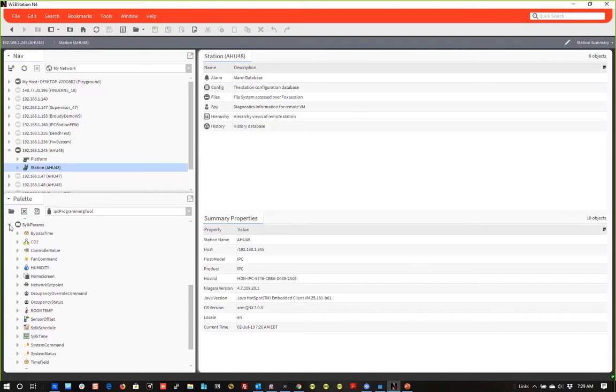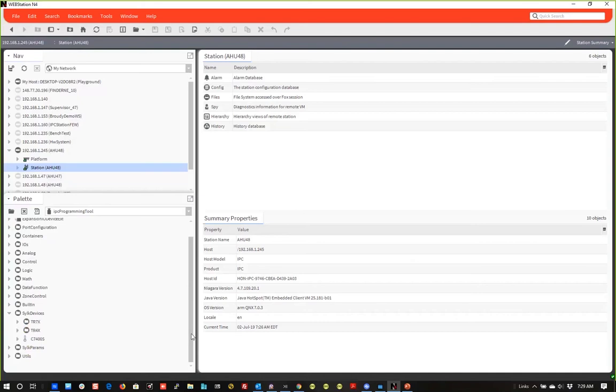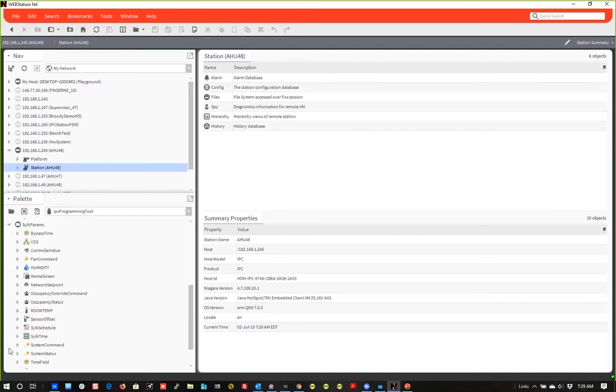One of the biggest differences, and I'm going to probably jump to the Spyder migrator first, because I think that'll make it easier. If you notice, we have these devices for the Sylk modules, for the ZIOs, but then you'll notice there's another one called Sylk parameters. These should look familiar to you. In the Spyder, there are slots on the ZIO itself. So in this controller, each of those slots on the ZIO becomes a separate parameter or a separate component or function block on your wire sheet.